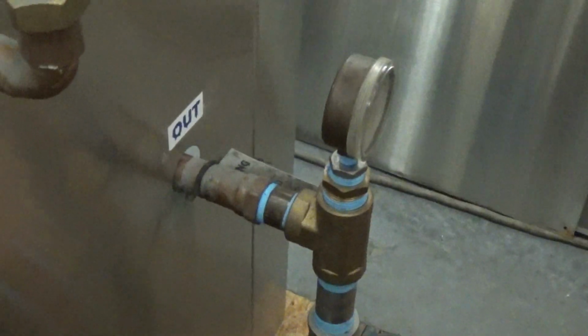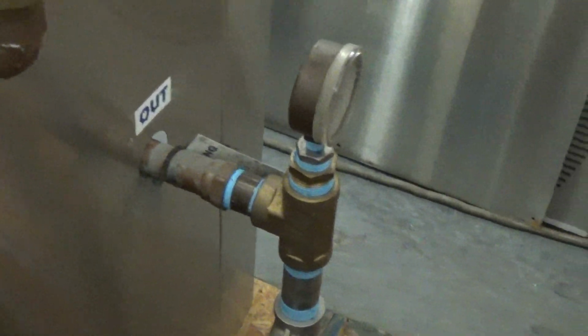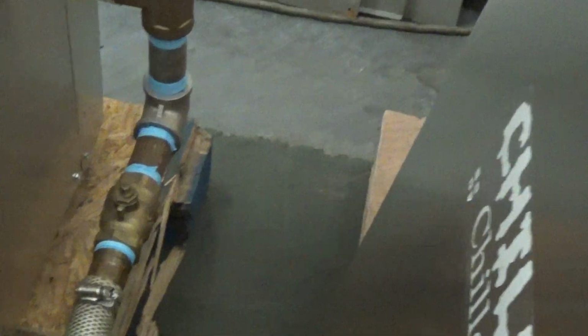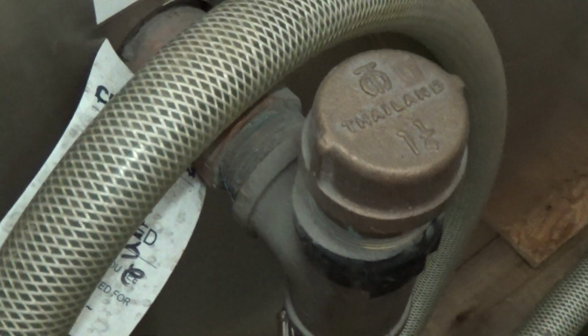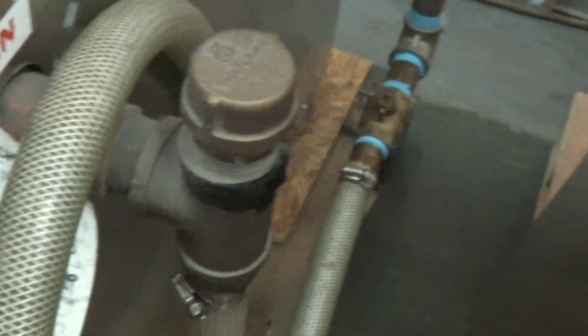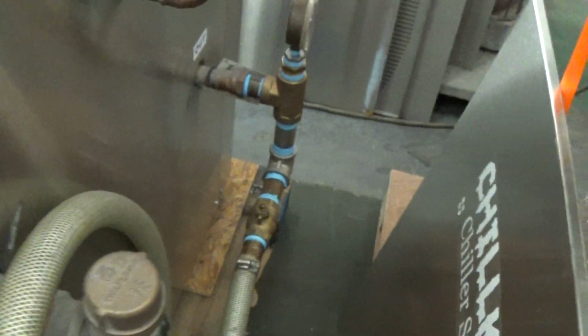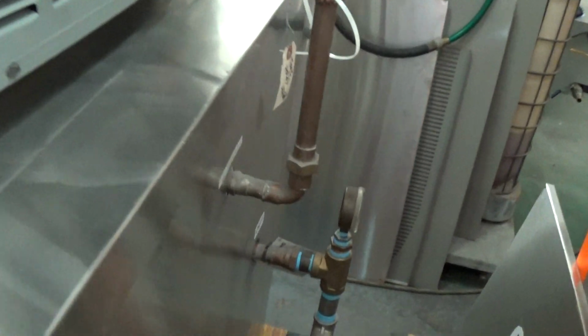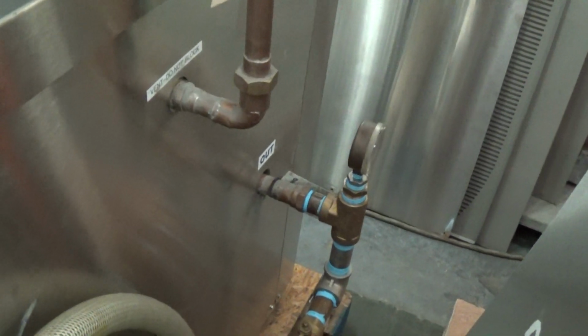We just set up a test loop when we run these in our shop, and that is the outlet. That's 1-inch NPT, and we just have it looped back. We have a valve to throttle it down a bit, and that just loops back to the return here, which is 1¼ inch female NPT. We have to throttle down the flow a little bit because without any restriction, the pump would spin a little bit too fast and possibly over amp.